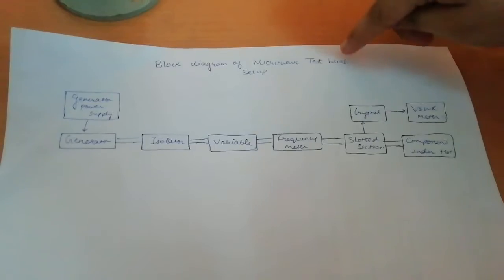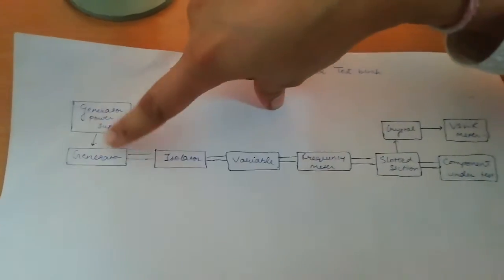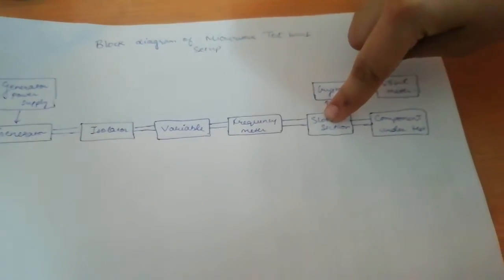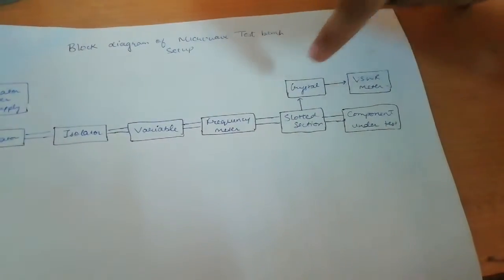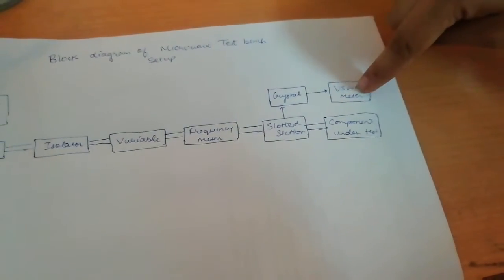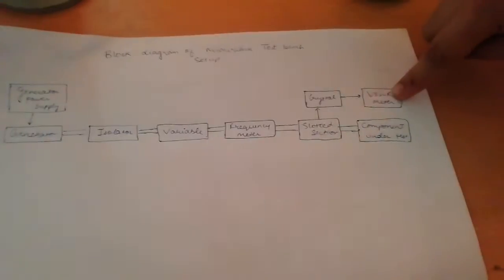This is a block diagram of the microwave test bench setup. First, generator power supply, then the generator, isolator, variable attenuator, frequency meter, slotted section, crystal detector, component under test, then VSWR meter which is voltage standing wave ratio.